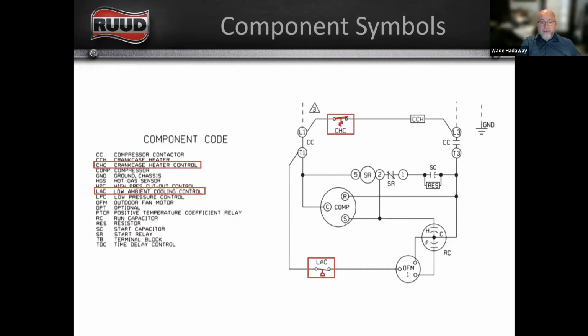The low ambient control is a pressure control, and that little semicircle with the line coming out of the top of it indicates pressure, right? So on the crankcase heater control, that squiggly line indicates temperature. On the low ambient, that semicircle indicates pressure. And you can see also that this is a normally closed switch. So by looking at this diagram, I can see that these switches are supposed to be closed. So when I start doing my troubleshooting, if I check across either one of these switches and they're open, then that lets me know that I have a problem.